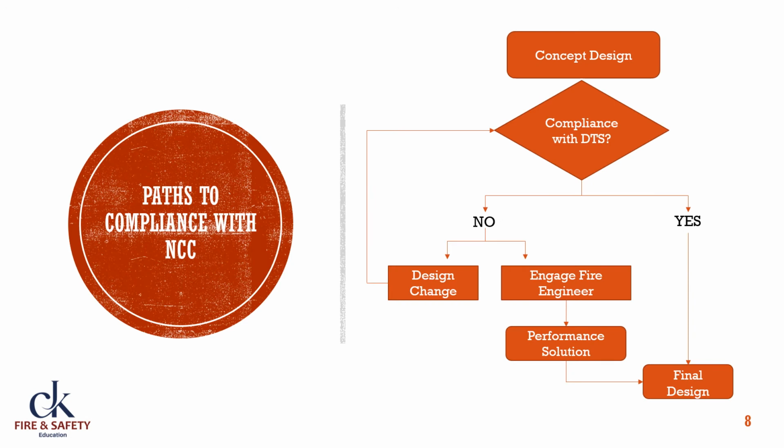The traditional approach to the NCC compliance is demonstrated in this flowchart. Talking about a new development, after a concept design is prepared, it is assessed by a BCA consultant who identifies any departure from the DTS provisions. If no departures are identified, the project team can proceed to the final design. If departures are identified, however, the project team may decide to change the design to follow this first path, or to engage a fire safety engineer who would prepare a performance solution demonstrating compliance with performance requirements.